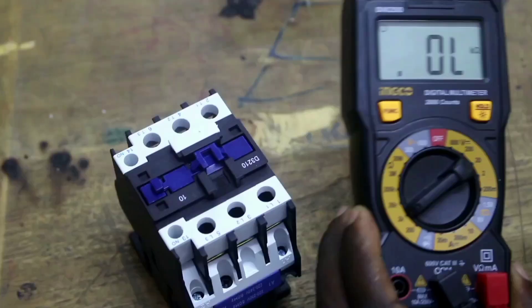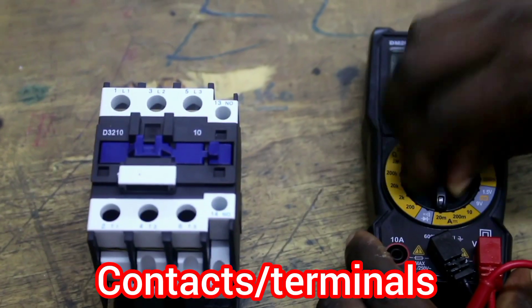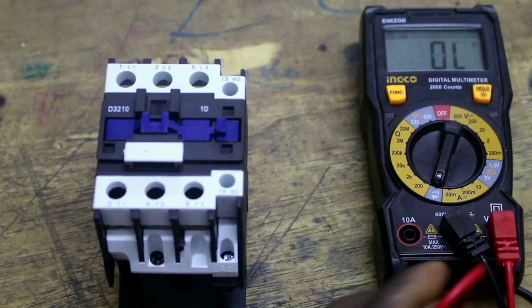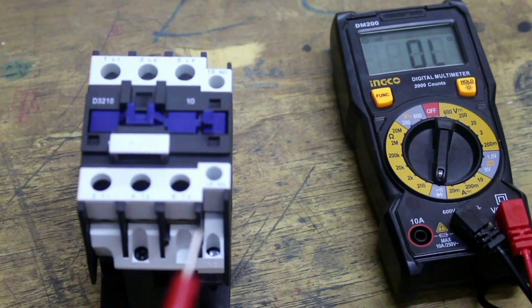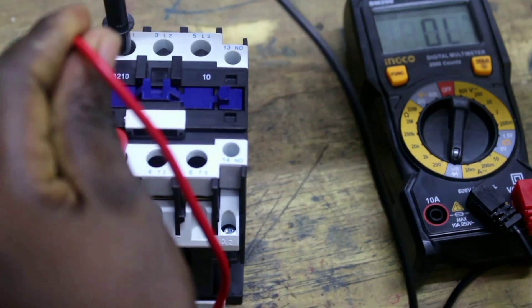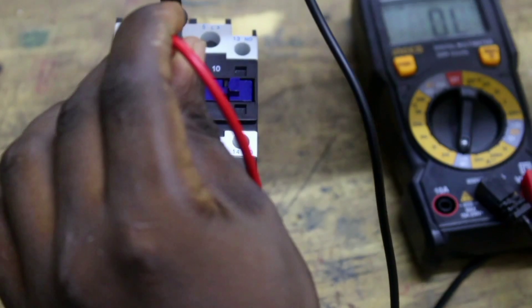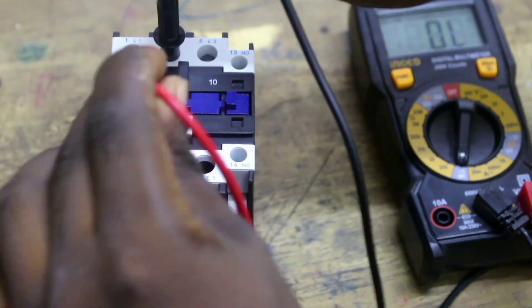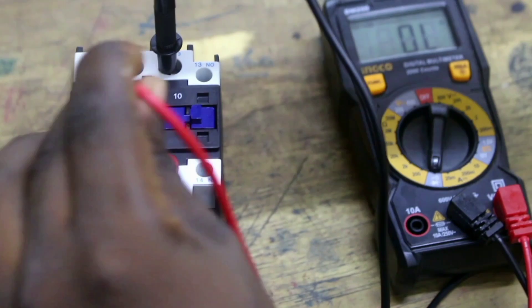The second test is to check the continuity of the contactor. Set your multimeter to continuity mode. When there is no power supply to A1 and A2, the contactor is not energized. Between terminal 1 and 2 there should be no continuity, between terminal 3 and 4 no continuity, and between terminals 5 and 6 there is also no continuity — as confirmed.